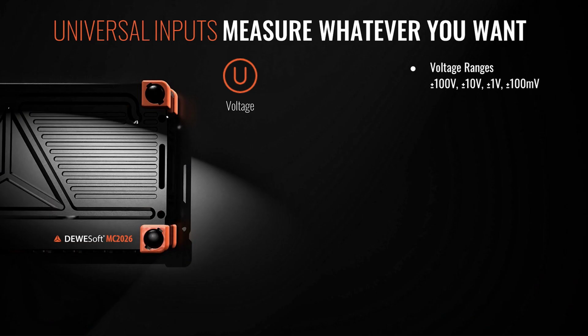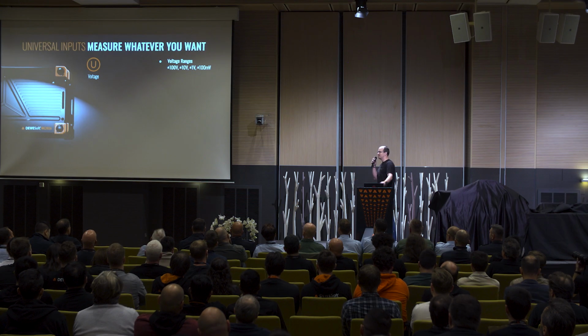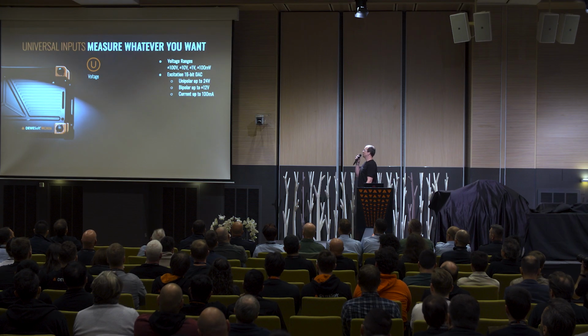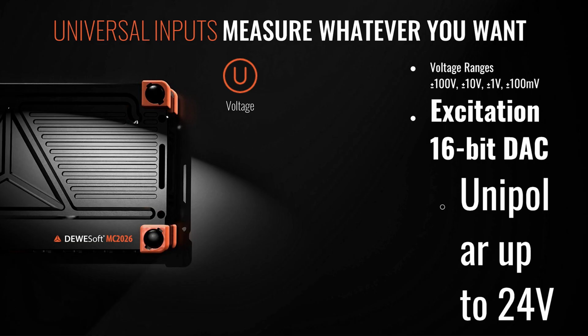But what does that actually mean in practice? You can measure voltages from plus minus 100 volts down to plus minus 100 millivolt. Very simple things, obviously you need to do that. We have excitation available, so you can supply your sensors with 24 volt unipolar excitation, plus minus 12 volts bipolar, and also a current excitation of up to 100 milliamps. It's also featuring a 16-bit DAC, so it can fine-tune in really small steps for specific applications. That's a nice benefit.